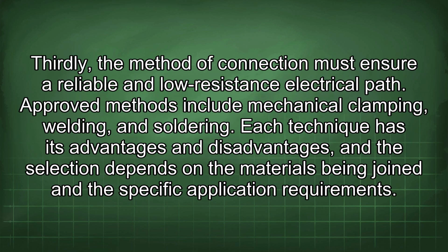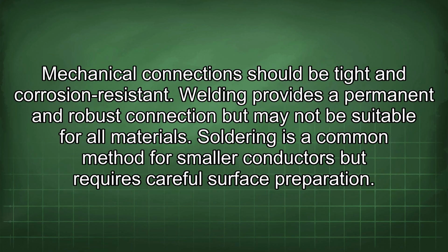Thirdly, the method of connection must ensure a reliable and low-resistance electrical path. Approved methods include mechanical clamping, welding, and soldering. Each technique has its advantages and disadvantages, and the selection depends on the materials being joined and the specific application requirements. Mechanical connections should be tight and corrosion-resistant. Welding provides a permanent and robust connection, but may not be suitable for all materials. Soldering is a common method for smaller conductors but requires careful surface preparation.